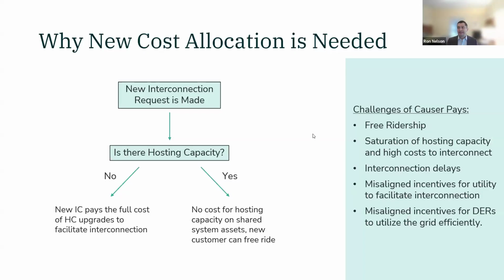For example, in April, when there's low load, export can backflow and create voltage issues that the utility has to address, or create backflow through transformers, which the utility has to address. That is a cost being caused by exporting facilities, and there's no price signal currently provided to get them to shift that export to a different time of day. I'm speaking generally, there may be a state that does this.